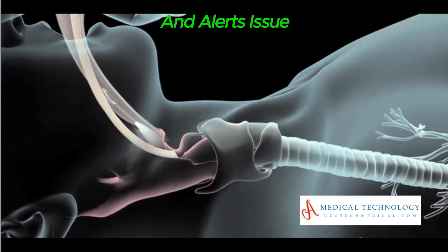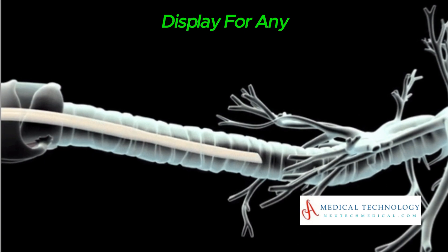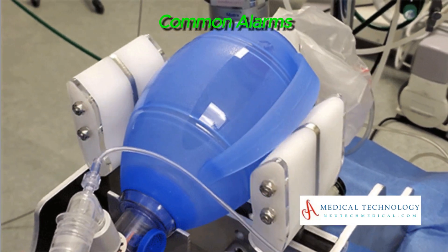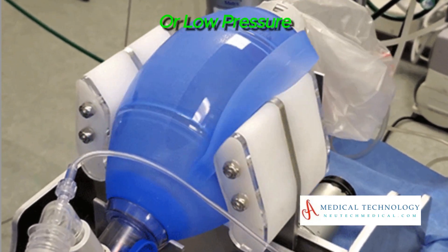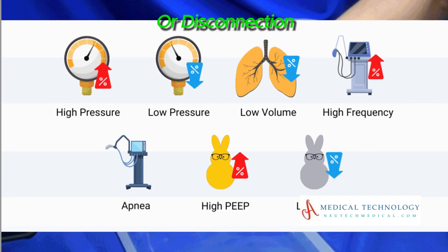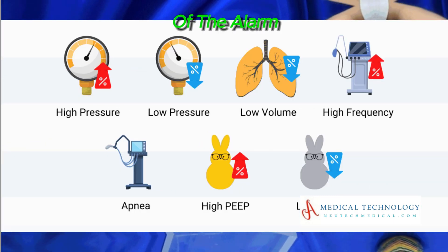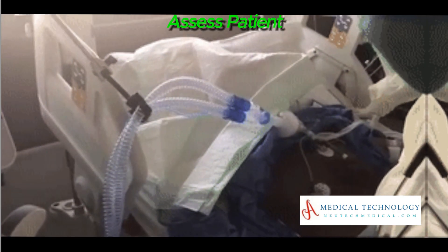Alarms and Alerts — Check the ventilator display for any alarms or alerts. Common alarms include high or low pressure, low tidal volume, or disconnection. Troubleshooting: Identify the cause of the alarm and address the issue. For example, check connections, assess patient condition, and reset the alarm as needed.